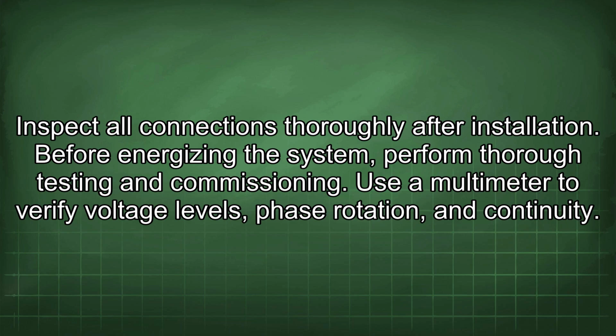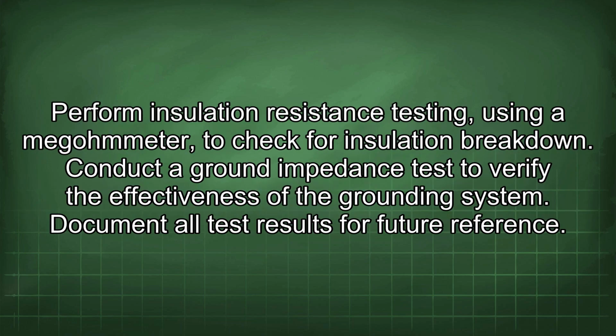Before energizing the system, perform thorough testing and commissioning. Use a multimeter to verify voltage levels, phase rotation, and continuity. Perform insulation resistance testing using a megohmmeter to check for insulation breakdown. Conduct a ground impedance test to verify the effectiveness of the grounding system. Document all test results for future reference.